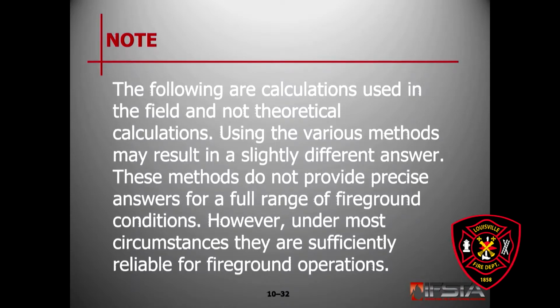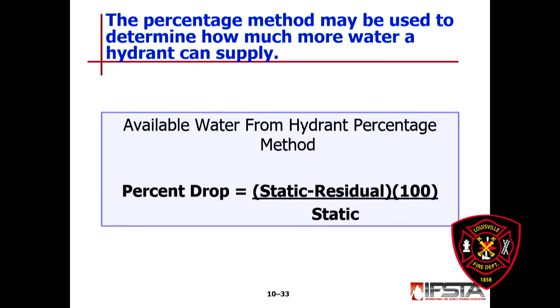So that's the percentage method. First thing you need to do is calculate the drop in pressure as a percentage. You take your static pressure, say it's 90. Then you lay one line and it drops to 70. So we take 90 minus 70, that's 20. We multiply that by 100, and then divide that by the static pressure. So static minus residual, multiply by 100, then divide by your initial static. So 90 minus 70, multiplied by 100, is 2,000. Divide that by 90, and it's 22.